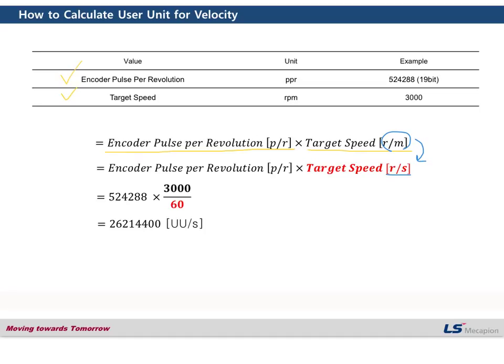Let's input the values. 524288, which is the encoder pulses per revolution, and 3000, which is the target speed. But we have to change the unit — minute should be converted to second, so we need to divide 3000 by 60. So we can get this value, and the unit is user units per second. That means the velocity for the L7NH drive — the output for the input.